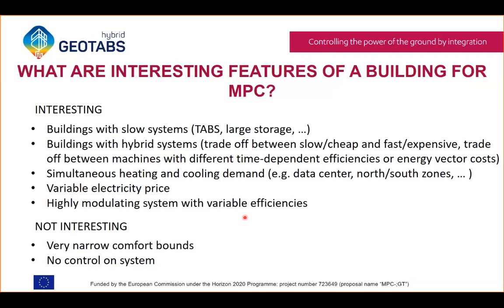What's not interesting for MPC is if you have very narrow comfort bounds. So if your room needs to always be between 21 and 22 degrees, for example, then there aren't many degrees of freedom, and MPC will not make a big difference. Another thing is that if there's no control on the system — remember radiators with thermostatic valves — that's not going to be interesting for MPC, as it cannot control it.